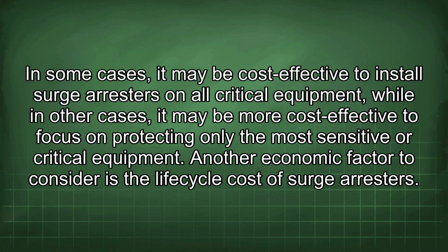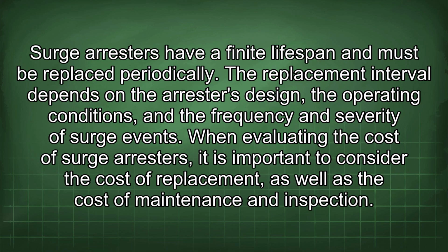Another economic factor to consider is the life cycle cost of surge arresters. Surge arresters have a finite lifespan and must be replaced periodically. The replacement interval depends on the arrestor's design, the operating conditions, and the frequency and severity of surge events. When evaluating the cost of surge arresters, it is important to consider the cost of replacement, as well as the cost of maintenance and inspection.